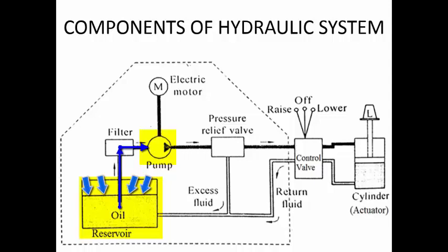Between the reservoir and the pump you have a filter. The function of the filter is to remove foreign particles or contaminants and to supply very clean oil into the casing of the pump. Because the gap between the moving elements of a pump is very small, if there are contaminants, there is a chance of causing damage and increased wear and tear. So in order to avoid all these things, the filter is used.